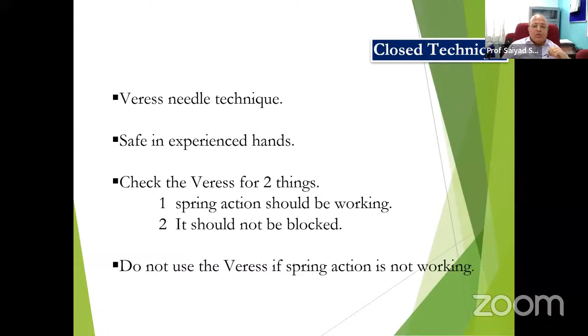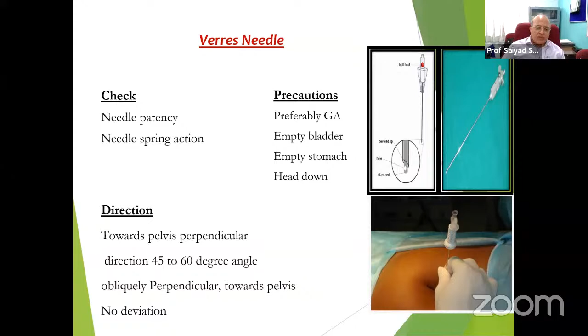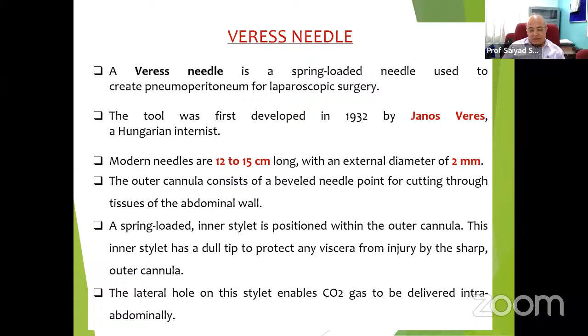Veress needle technique is safe in experienced hands, and check 2 things: the spring action of the Veress needle should not be blocked. Don't use a Veress needle if the spring action is not working. You see the Veress needle, and the direction of the Veress needle, you see in the last picture, towards the pelvis, perpendicular direction, 45 to 60 degree, afterwards obliquely perpendicular towards the pelvis, no deviation. The qualities of the Veress needle: 12 to 15 centimeter long, 2 millimeter in diameter. The spring-loaded inner stylet is positioned within the outer cannula. This inner stylet has a dull tip to protect any viscera from injury by the sharp outer cannula. The lateral hole on the stylet enables carbon dioxide gas to be delivered into the abdomen. Now, how to check?